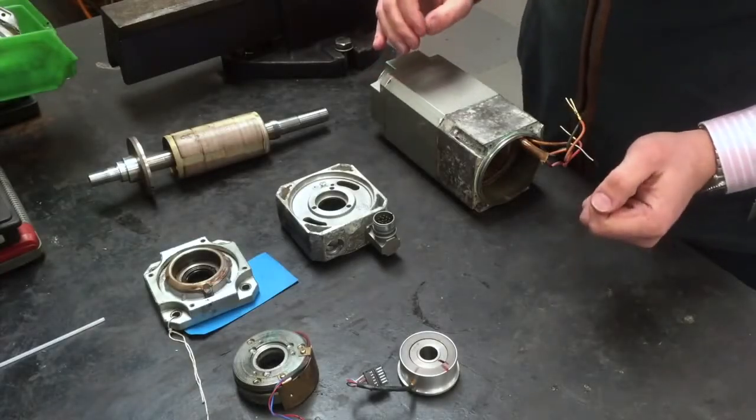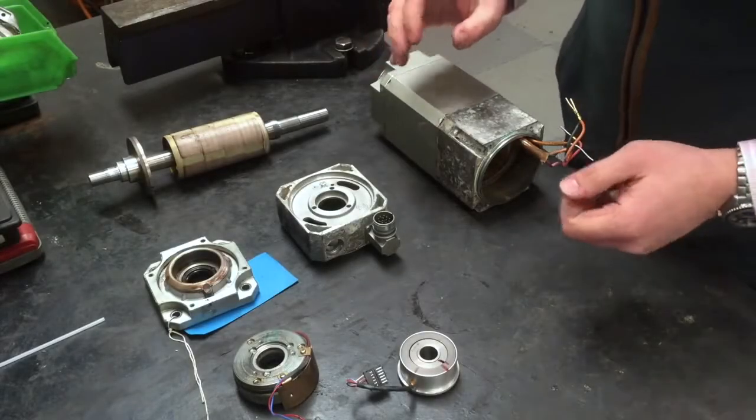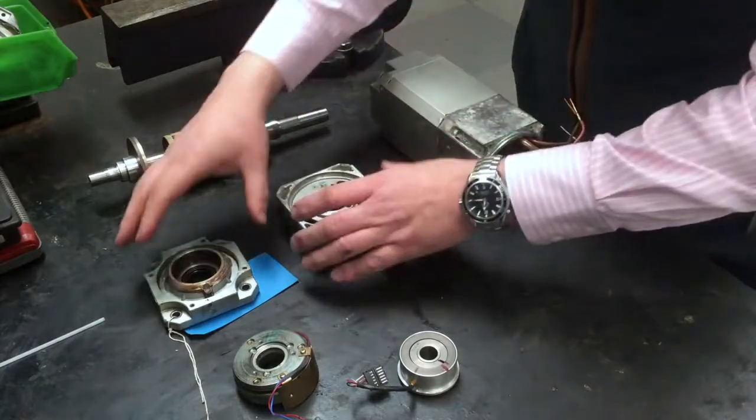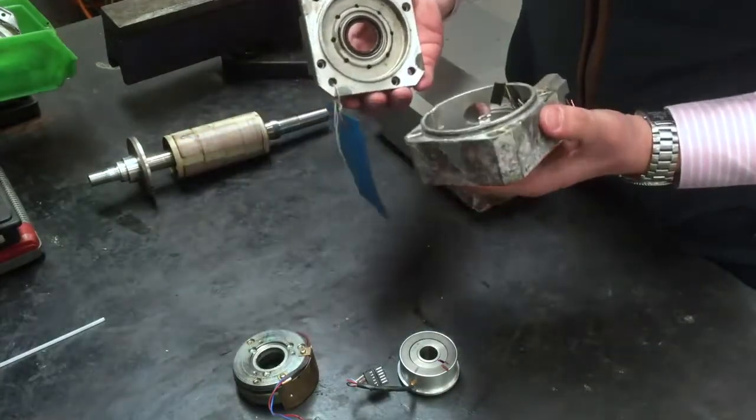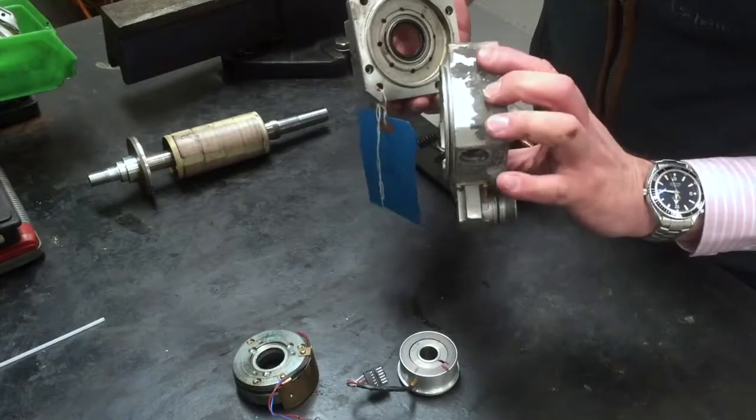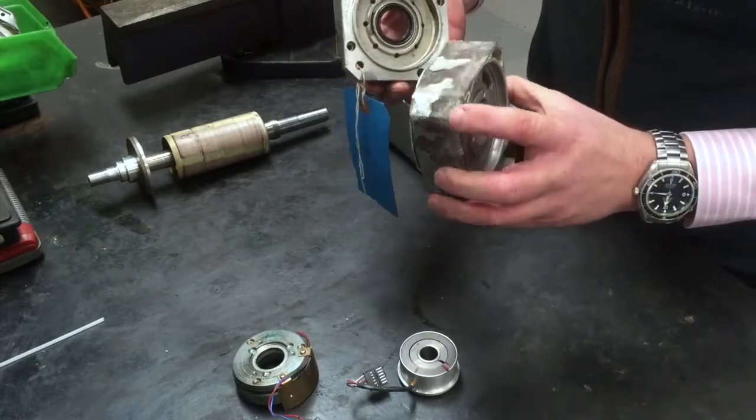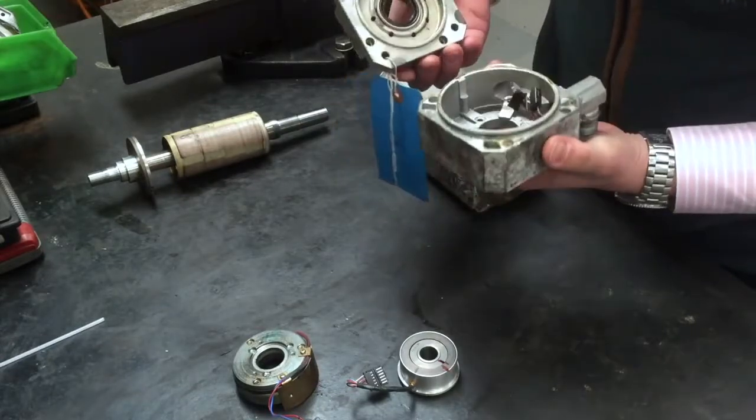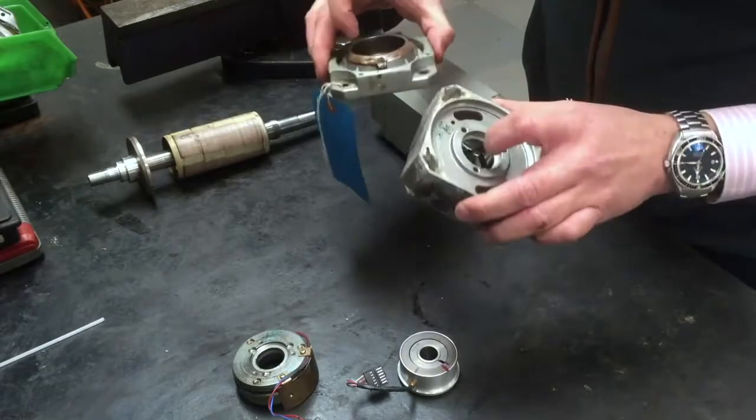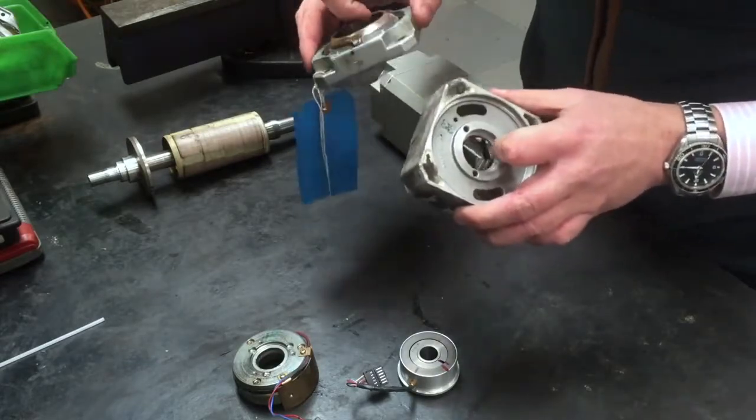As you can see, the servomotor has now been stripped down into component parts. A number of things will happen here. Firstly, we will take the end shields. You can see there are elements of corrosion on here, as if there is water or fluid that has been around the motor. We will clean these up and measure the bearing housings on our coordinate measuring machine.